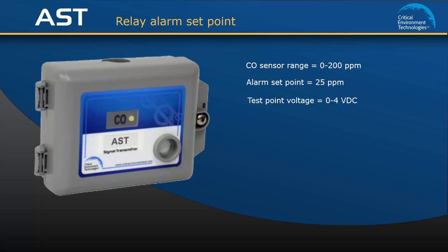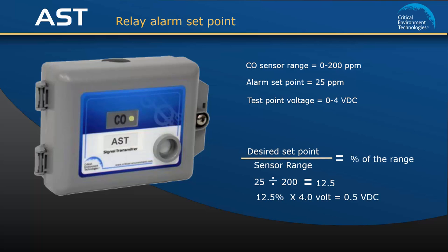We need to find out what voltage equals the alarm set point of 25 ppm. To do this we use the formula shown on the screen. The desired set point value is 25 ppm and the sensor range value is 200 ppm. 25 divided by 200 equals 12.5% of range. Multiply this value by 4 volts, and the test point voltage setting to achieve an alarm set point of 25 ppm is 0.5 volts.